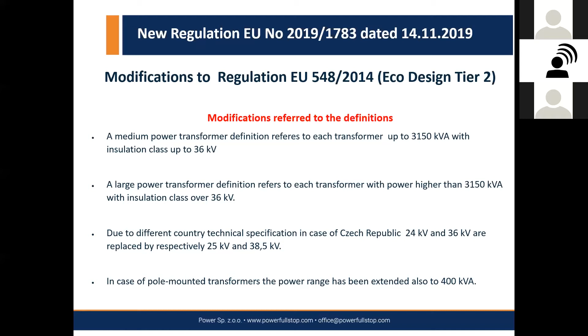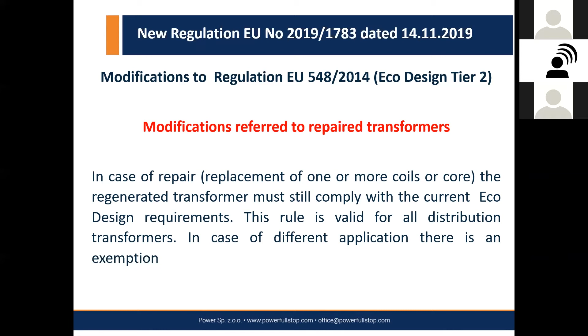This is also maybe an interesting point for you, about repaired transformers. In case of repair, replacement of one winding or of the core, the regenerated transformer must still comply with current ecodesign requirements. This is a very important point that was not mentioned in the previous regulation - it's new here. The rule is valid for all distribution transformers. In case of a different application, it's treated as an exemption. So if we are repairing a big power transformer, this does not apply to that kind of transformer.